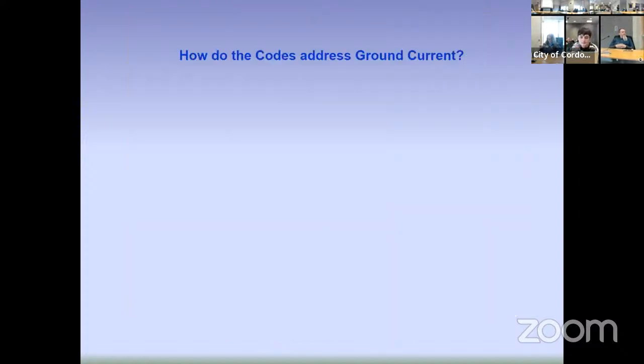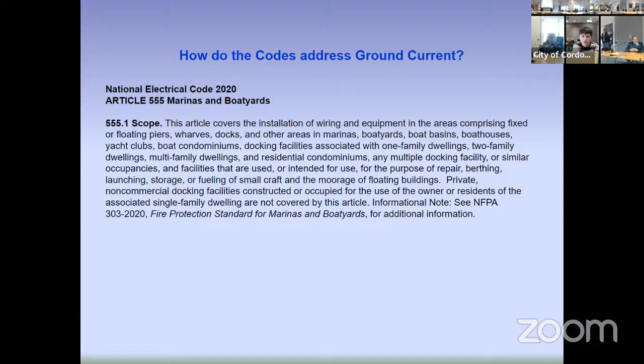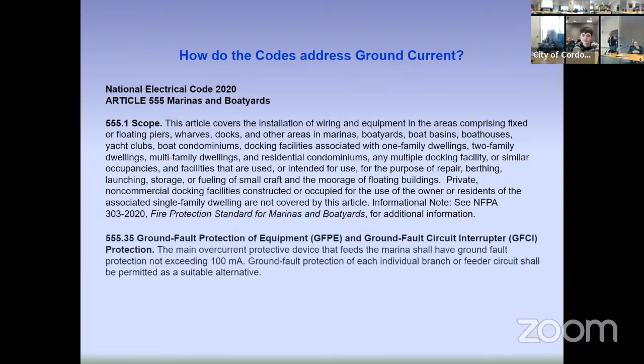So how do the codes address the ground current? Let's bring this next one up. This is what we have to abide by with the code. This is Article 555 in the National Electrical Code. And this just talks about where we have to comply with these codes. Let's go to the next one. And this talks about the required ground fault protection. So feeders are required to be 100 milliamps max, and the shore power is required to be 30 milliamps max.